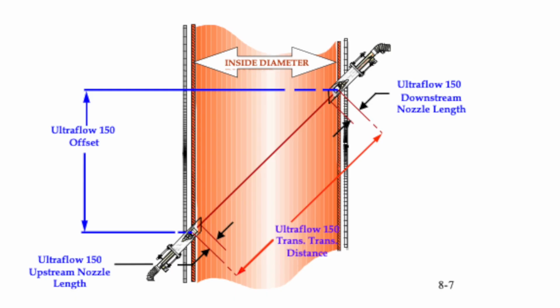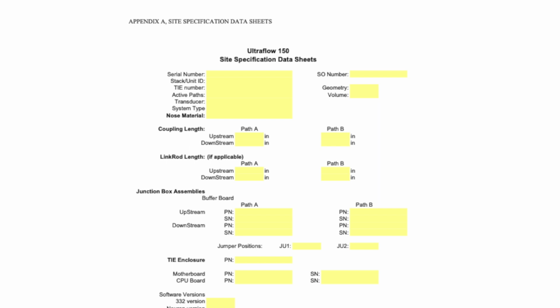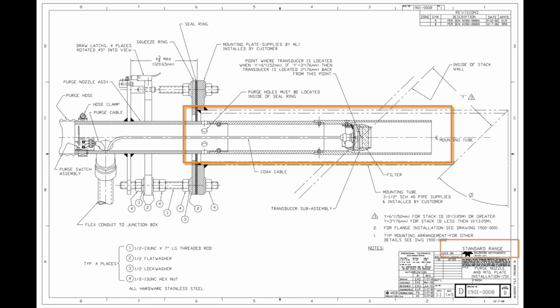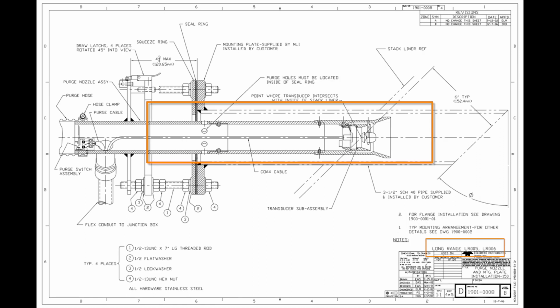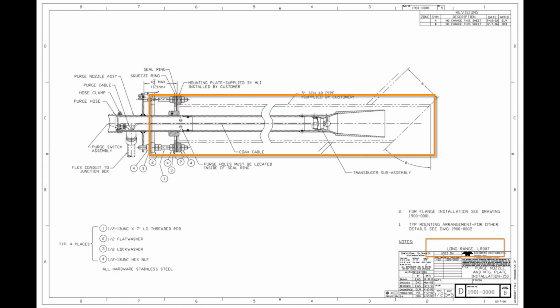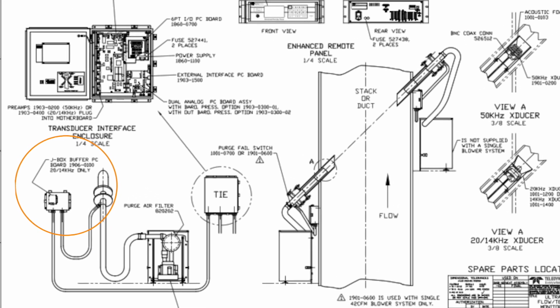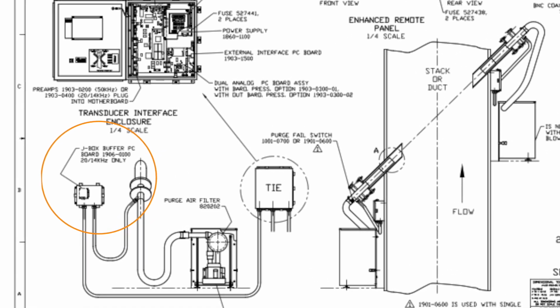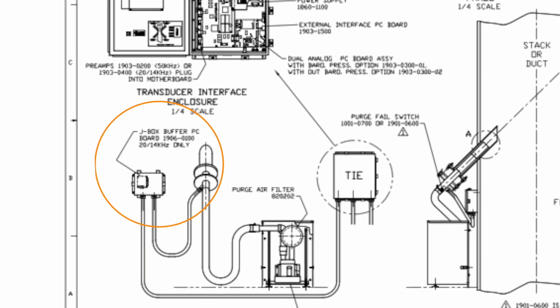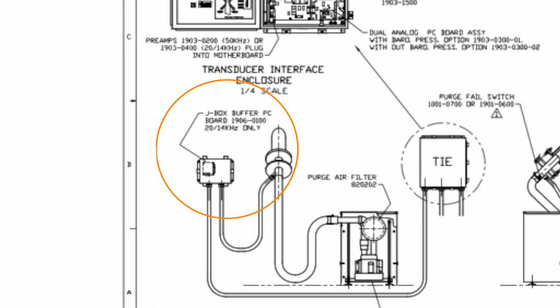Along with stack geometry, effluent composition and temperatures require that several different types of ultrasonic transducers be used. Refer to Appendix A in your manual to see what transducers are used in your particular monitor. The options include electrostatic transducer, long-range transducer, and extended long-range transducers. If using long-range or extended long-range transducers, a preamp board will also be required between the transducers and the tie box.